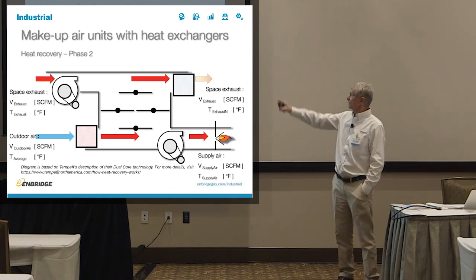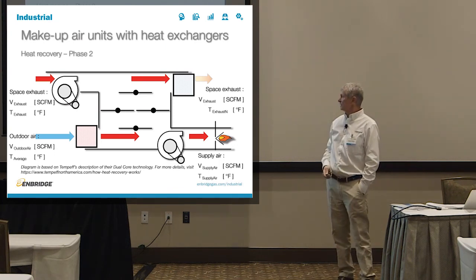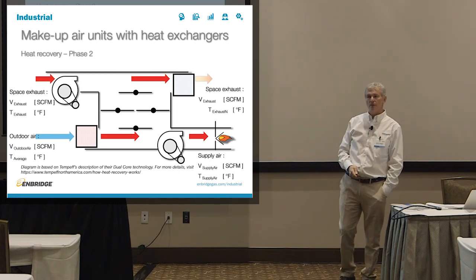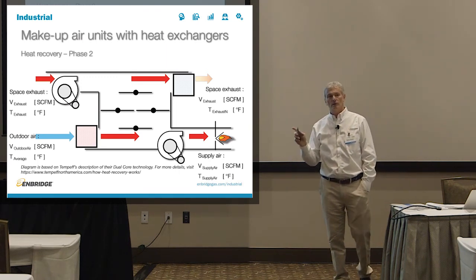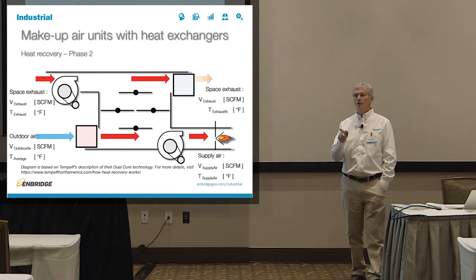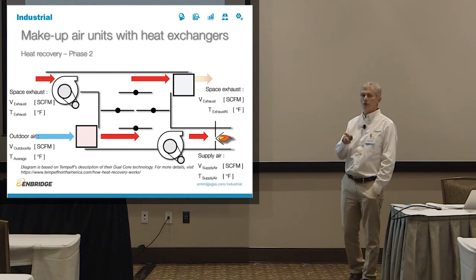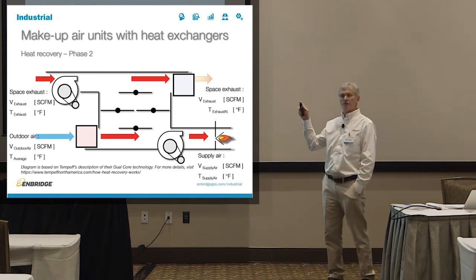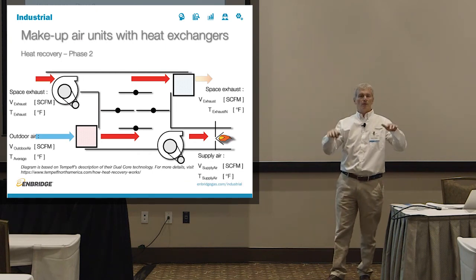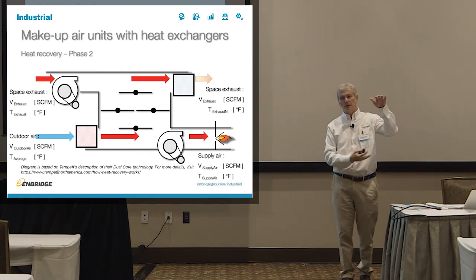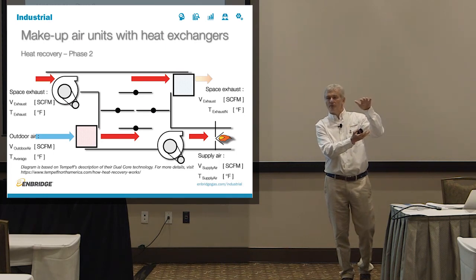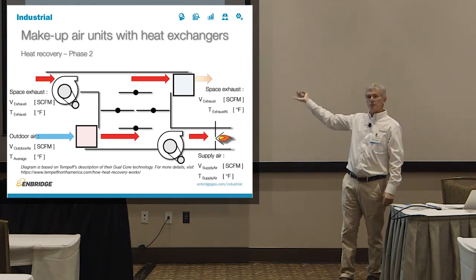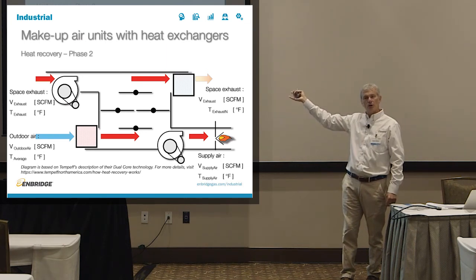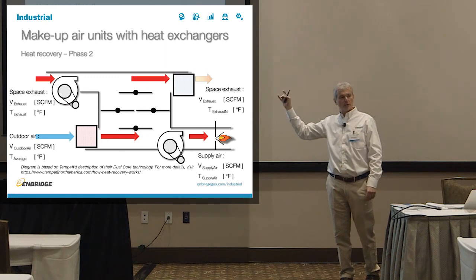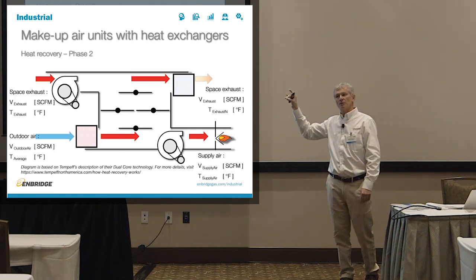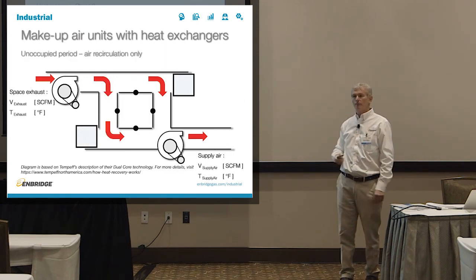Now the space exhaust preheats the other core, and the core that was just preheated is being used for the outdoor air to preheat it again. And every 2 minutes, that switches. For those of you familiar with pollution abatement technologies, this is how a regenerative thermal oxidizer works. Two beds: one is being preheated with exhaust while the other one is preheating the incoming air for the recovery. Same thing here. These keep switching every 2 minutes. And because they keep switching so often, there is no frost buildup on them. Frost doesn't have time to build up. Or so they tell me.